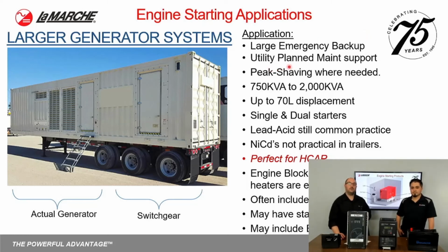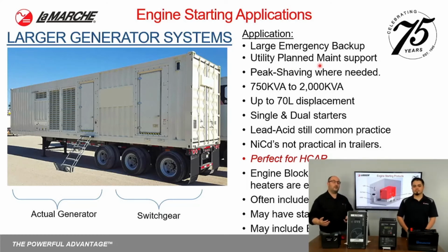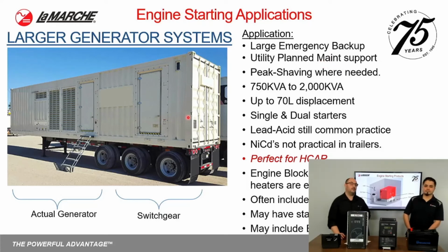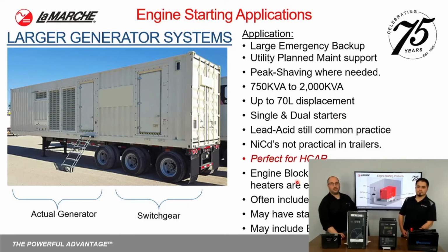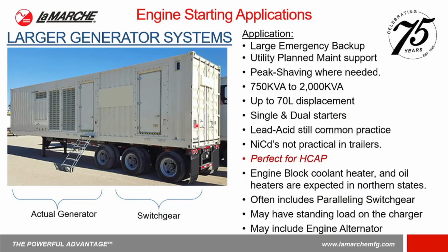Or even if you're a utility running planned maintenance, but you have a highly critical customer that you need to support. So if you're doing something large like changing out a transformer for a utility, but you need to keep that customer going, you're going to be pulling a trailer to supply the customer. This is a perfect application for an HCAP, not only because of the low self-discharge, but also because of the energy footprint and the available power that's really available to crank and start up that engine.